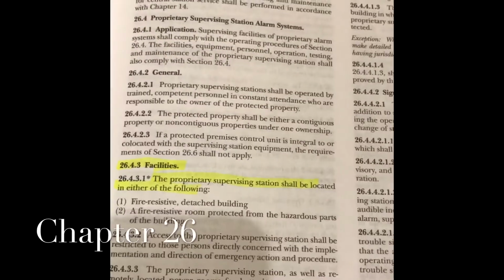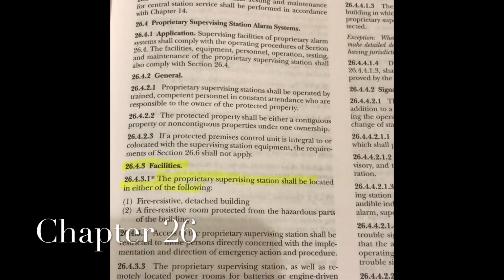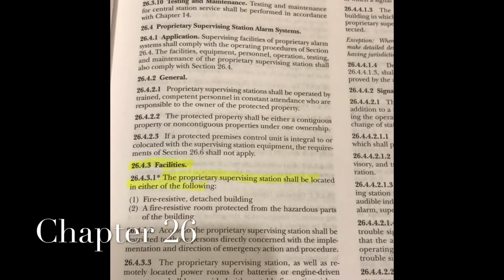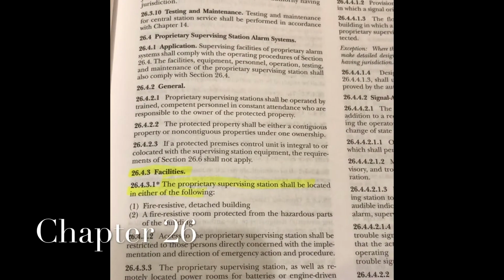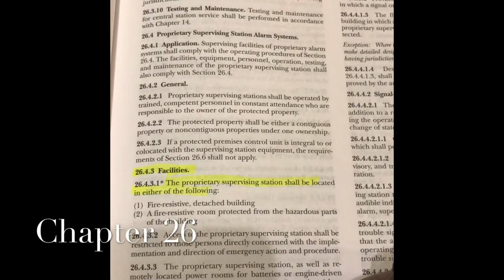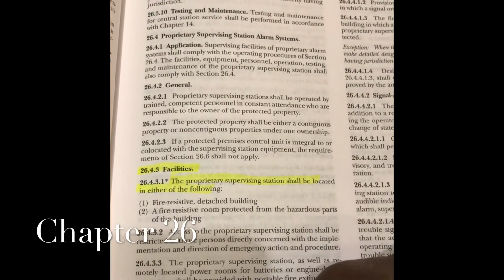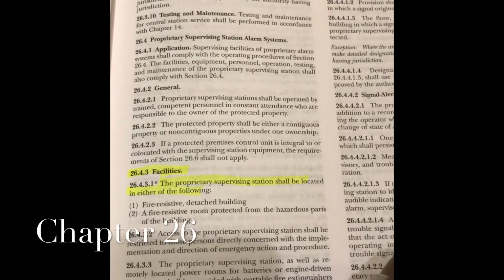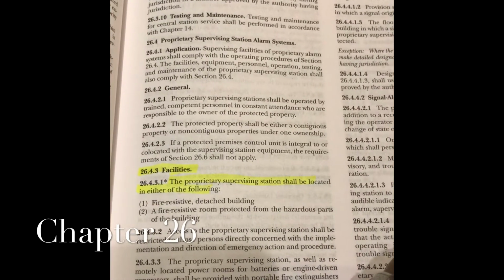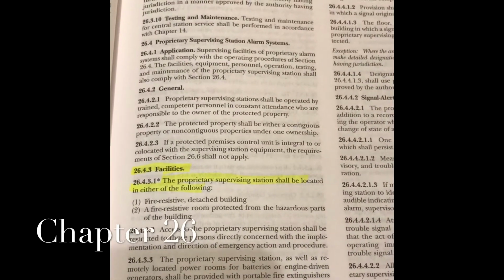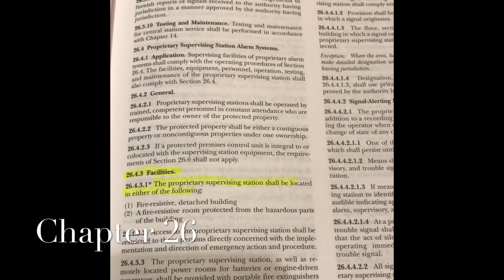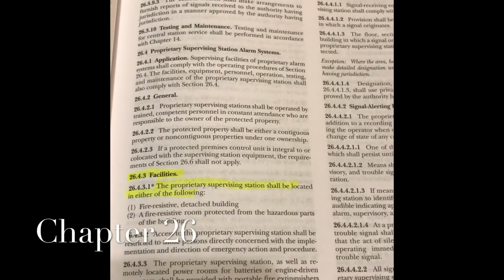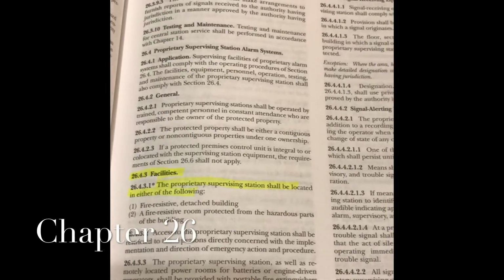If we go to right here, facilities, section 26.4.3.1, if you read through this section, that deals with everything that is dealing with the proprietary station. A proprietary station is basically a company that pretty much monitors their own signals, and they are the ones who call the police after they've had someone go out to investigate it.